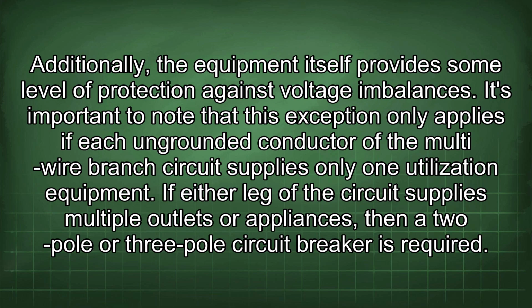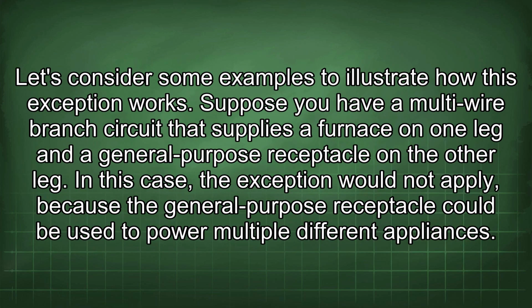It's important to note that this exception only applies if each ungrounded conductor of the multi-wire branch circuit supplies only one utilization equipment. If either leg of the circuit supplies multiple outlets or appliances, then a 2-pole or 3-pole circuit breaker is required. Let's consider some examples to illustrate how this exception works.